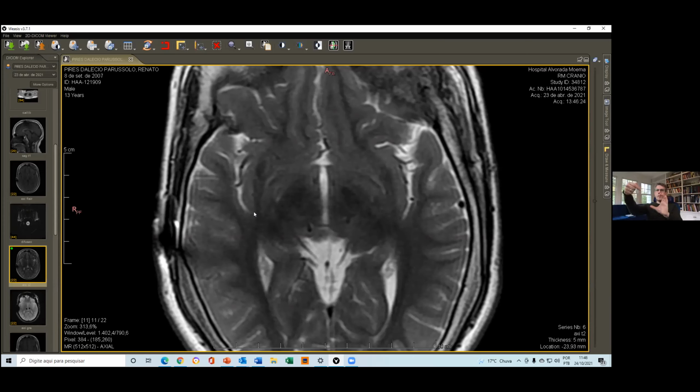So, I'm just talking about the axial movement of the pin, because now the pin could move on its axis. Yeah, that's correct. But even if the fourth pin would move, the other three will keep the head likely in the same position. So I don't think the stereotactic coordinates were damaged by having this pin in. Even if this pin has moved a little bit, the other three, I think, will do the job.